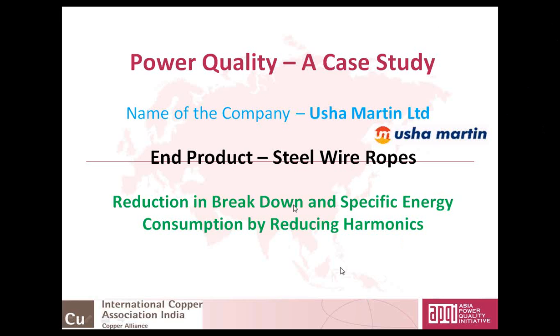As explained by Mr. Srinivasan, you know, what is power quality disturbance. There are some electrical devices in the plant which alter the frequency of the sine wave and distort the current and voltage. This distortion may come in different forms. The disturbance can be called dips or swells or notching or impulse or oscillation, like this. And the causes of power quality problems, as I mentioned on the slide, are non-linear loads, local resonance, capacitor switching, load switching, etc.